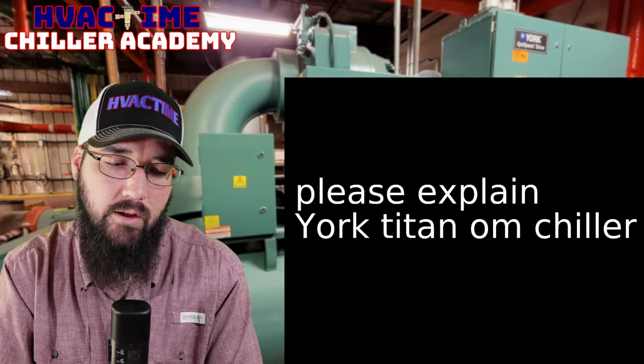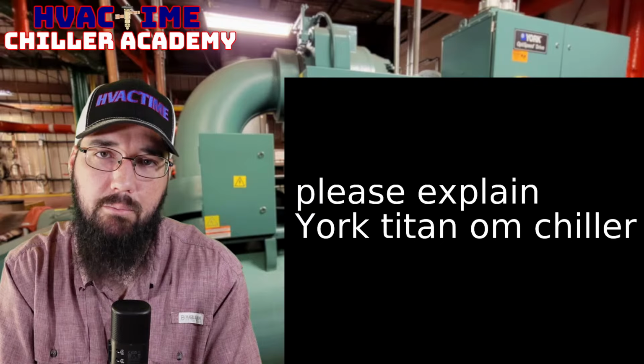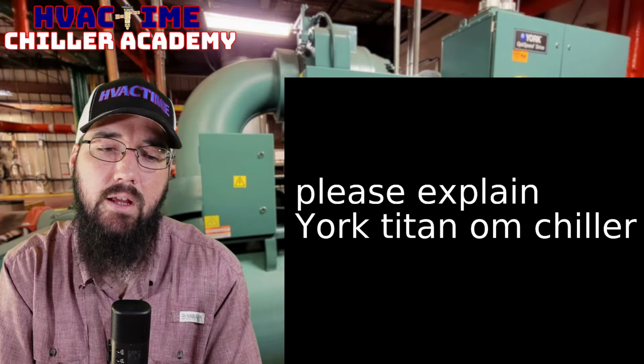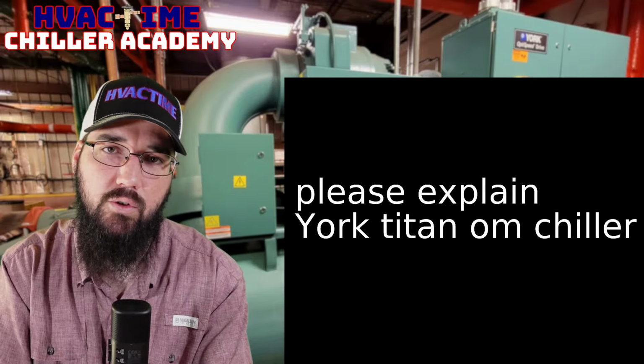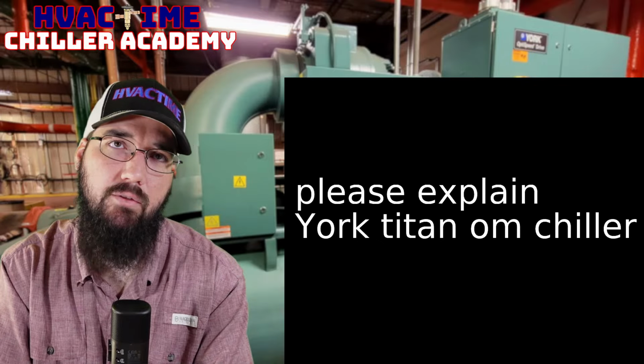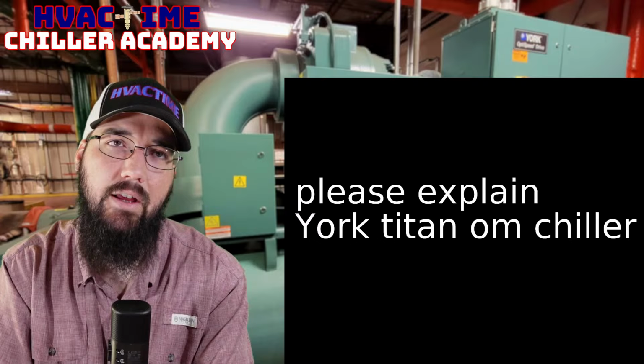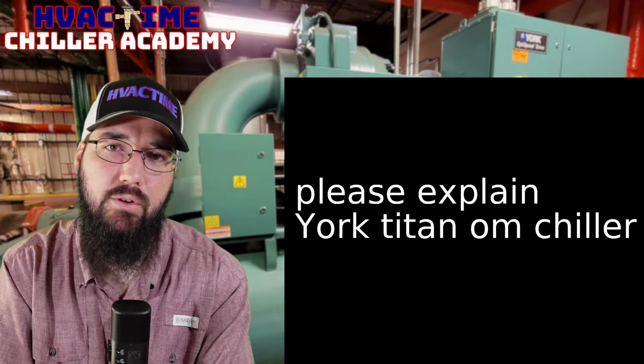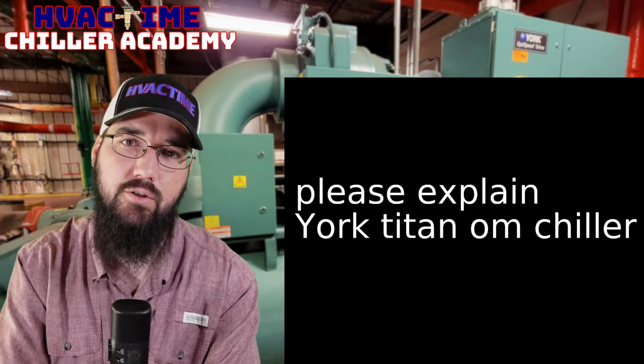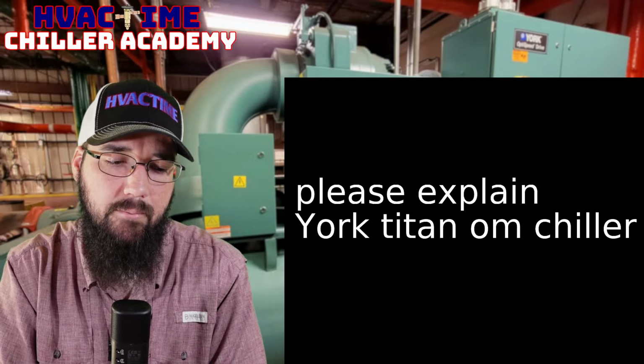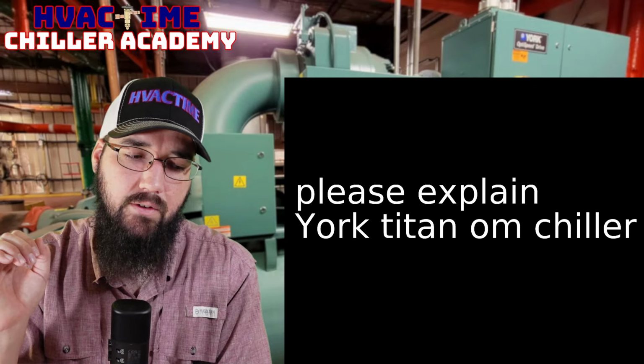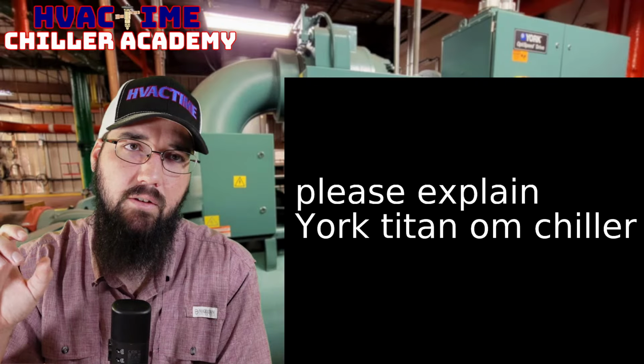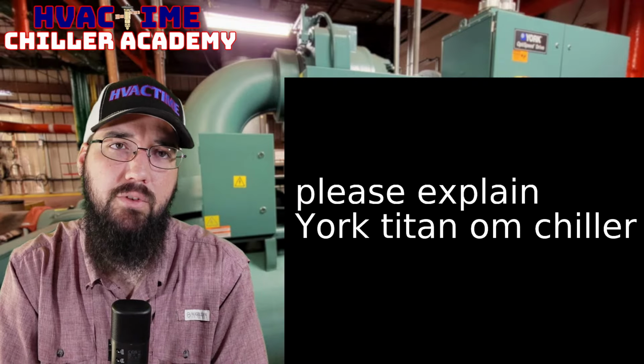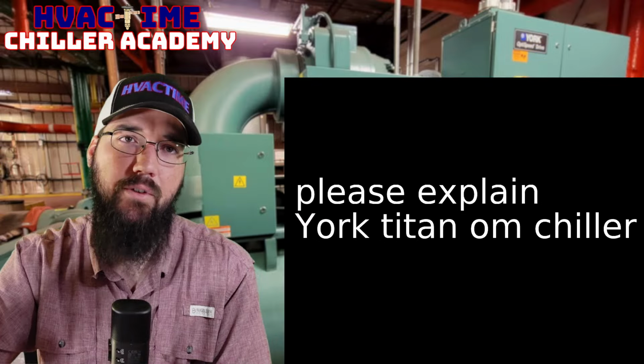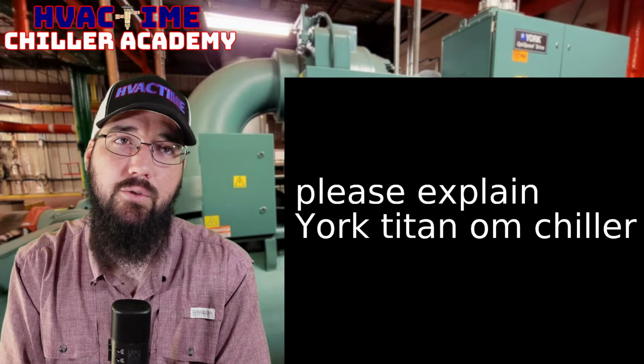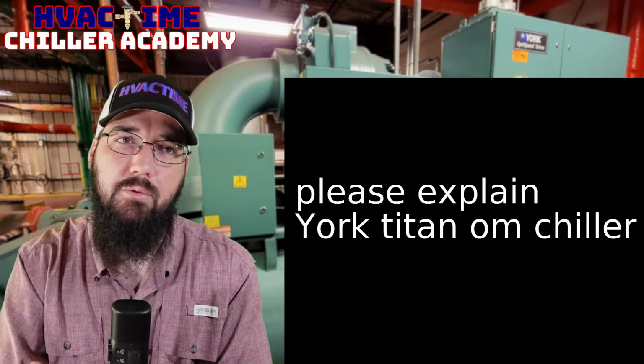So with these OM machines, the compressor and the oil sump are built into one main package on the machine itself. That's something to be aware of: your actual oil sump, at least for the York specifically. Some of the others may do it a little bit differently, but York has their oil assembly built into the compressor housing, and then you have your suction and discharge gas coming through and out. Most everything else about the process is the same basic thing. You have the condenser on top that flows down into the evaporator through its metering valve, comes back into the compressor, makes a solid loop.